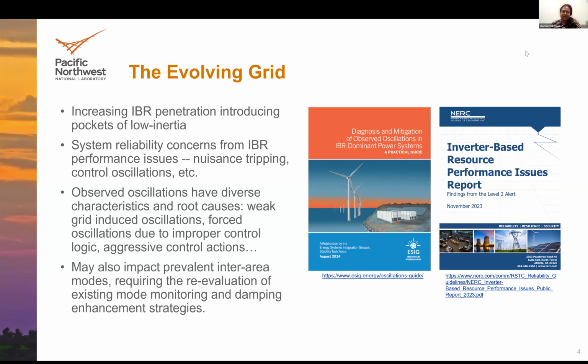And another way the IBRs impact oscillations in the power grid interconnections is that they may impact the prevalent inter-area modes. For example, the inter-area modes that are present in the power system today are mostly influenced by where synchronous generators are located and how groups of generators are exchanging energy among each other at a low frequency, and those appear in the system as low frequency oscillations. But if synchronous generators in particular areas are being replaced with inverter-based resources, then the loss of rotational inertia can change the properties of these modes. And because these modes have been studied, the monitoring and control actions that are in place today with these operations may need to be re-evaluated.